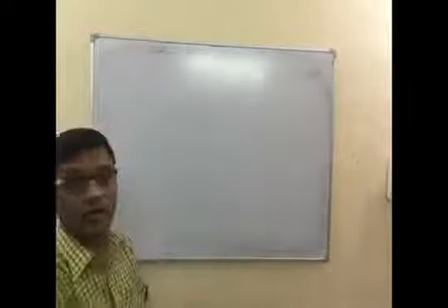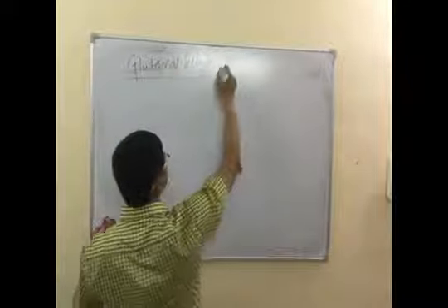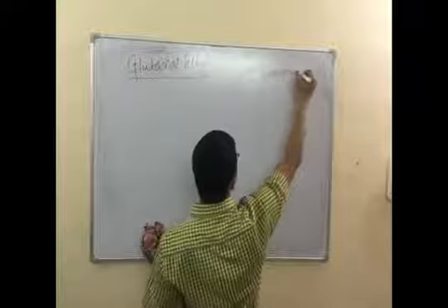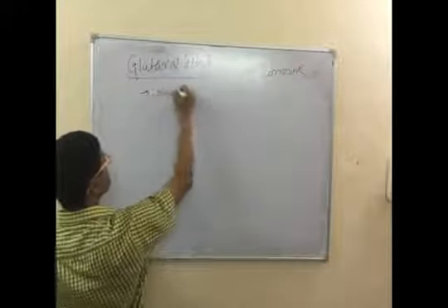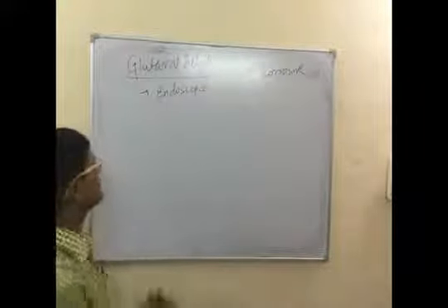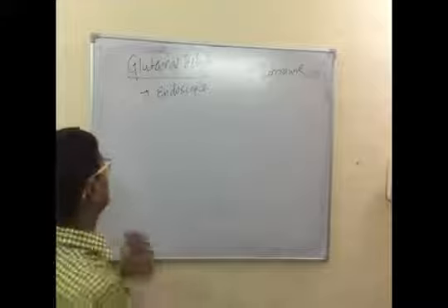Because it is corrosive to metal, formaldehyde is not recommended for sensitive instruments like endoscopes. For this purpose, the best method is glutaraldehyde. Glutaraldehyde is equally efficacious like formaldehyde, but it is less corrosive. Hence, it is best for endoscopes. Various endoscopes, cystoscopes, bronchoscopes, laryngoscopes, all these are better sterilized by glutaraldehyde.